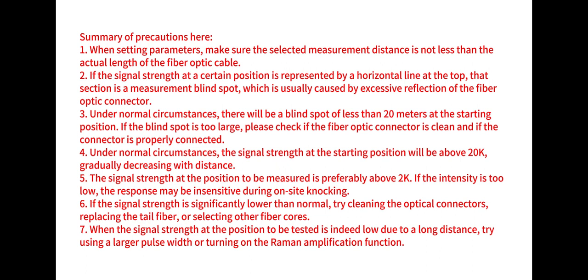Summary of precautions here. 1. When setting parameters, make sure the selected measurement distance is not less than the actual length of the fiber optic cable. 2. If the signal strength at a certain position is represented by a horizontal line at the top, that section is a measurement blind spot, which is usually caused by excessive reflection of the fiber optic connector. 3. Under normal circumstances, there will be a blind spot of less than 20 meters at the starting position.